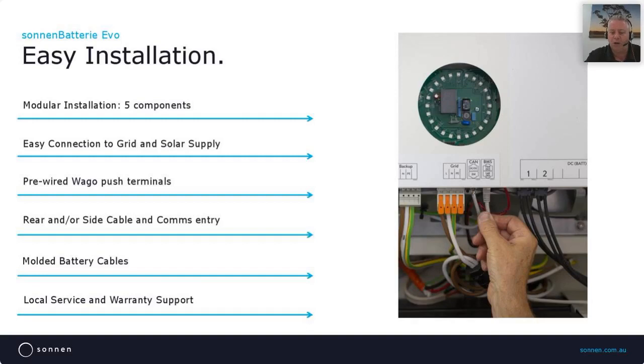Easy installation was a key requirement of sonnenBatterie Evo, and this has been achieved by maintaining a modular design, reducing the total weight of the system. Rear and side options for cable and comms entry. This allows for neat installs, whilst flexibility in design depending on the site requirements. Pre-wired Wago push terminals for quick and easy connection, and molded battery terminals for quick and easy connection as well. Local installation, service and warranty support based in Adelaide, with a growing team of technical and customer service agents. We also have an in-house engineer that can assist with system design, and we have a local installer trainer available to support your future installations.